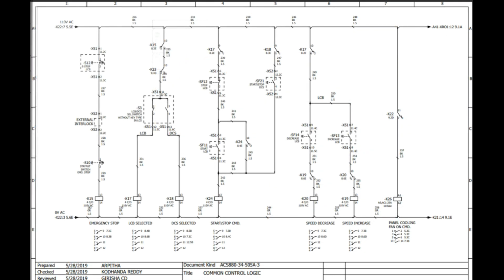Guys, the next page is very important and it is named common control logic. Here we can see two lines. The top line is 110 volt AC and the bottom line is 0 volt. We'll start with the left hand side. The very first tapping you can see here is X51 channel number 1 and 2, and in between that there is the emergency stop button for the LCB, local control box. Generally in normal condition it will be NC because the push buttons are not pressed. If it is NC, 110 volt will get to the external interlock.